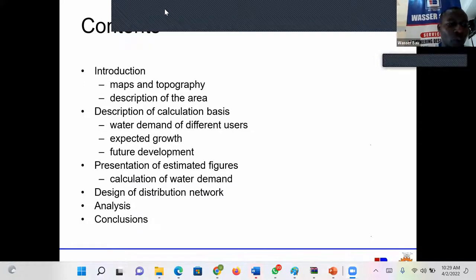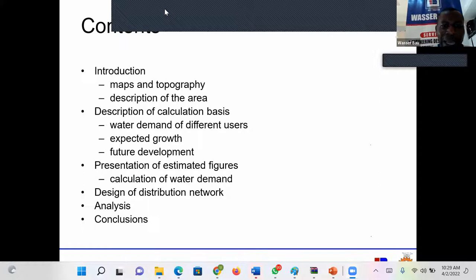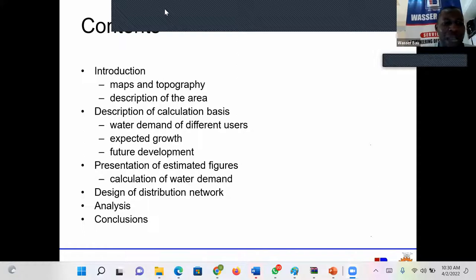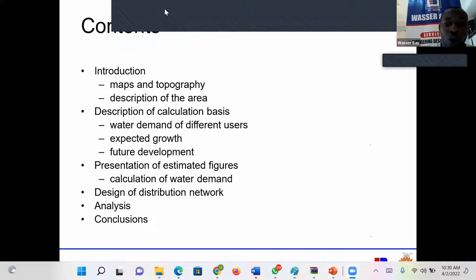You must pump water to the upper reservoir so that during distribution it will go by gravity. The next thing you need to do is calculate your water demand. In calculating your water demand you must take cognizance of three things: the basic daily usage of the riparian community, expected growth, and future developments. In design you must design for worst case scenario - you must design for the maximum allowable water demand.